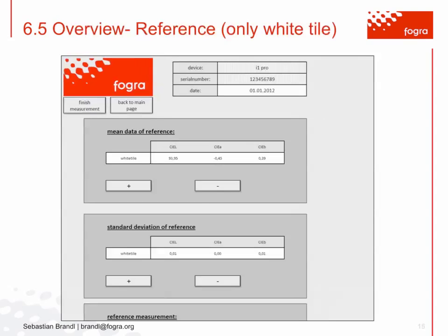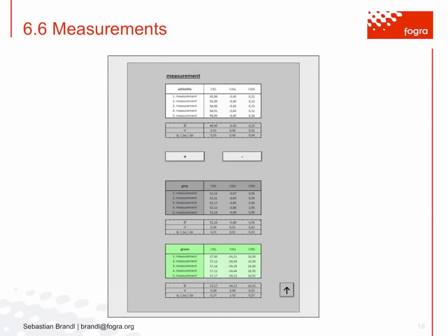Okay, we talked about that. The standard deviation might be used as a starting point for the uncertainty assessment when you multiply this standard deviation by 2 or 3 or more. We recommend 3 at the beginning to get some tolerance values for your own individual drift detection.